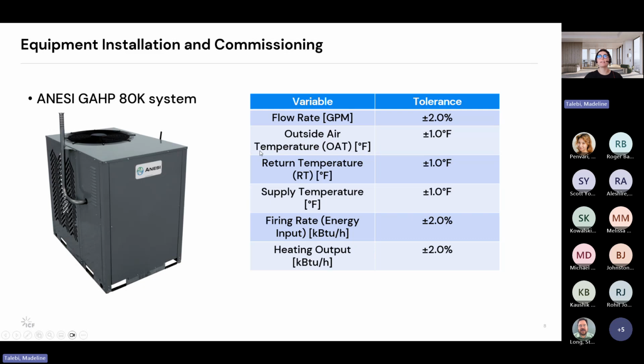Overall, for any rates that I have listed here, so the flow rate, the firing rate, the heating output, we're going to look at a ±2% tolerance. And for any of the temperatures, so that being outside air, return, supply, we're looking at ±1 degree Fahrenheit. And according to the commissioning, everything was in positive agreement with those tolerances that were set beforehand.